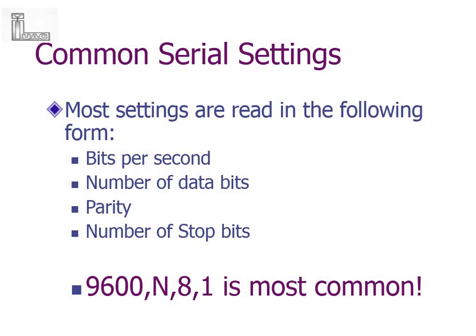Common serial settings are read in the following form: bits per second, number of bits, parity, and number of stop bits. A common protocol is 9600N81, which you can see in most instrument manuals.